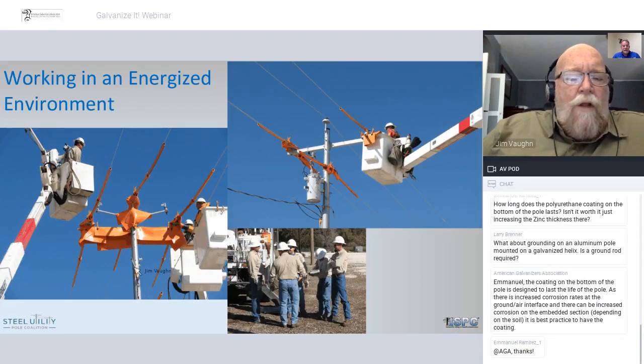And there's one other thing that you can do here with these steel poles that a lot of linemen don't recognize. You can take these pole plastics that we showed you earlier. We're allowed to cut pole plastics off with a hacksaw or sawzall and make a 2 or 3 foot long section, and that allows us to snap that right onto that pole and provide cover up on these steel poles when we're doing this cover. So I want to encourage you to do that.